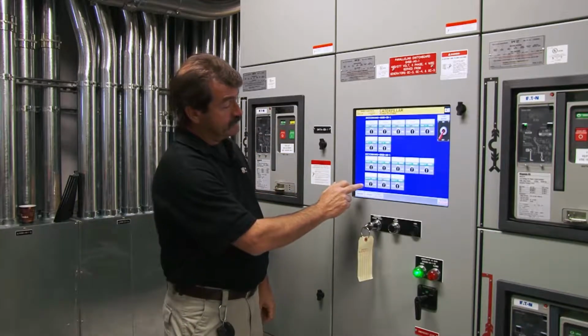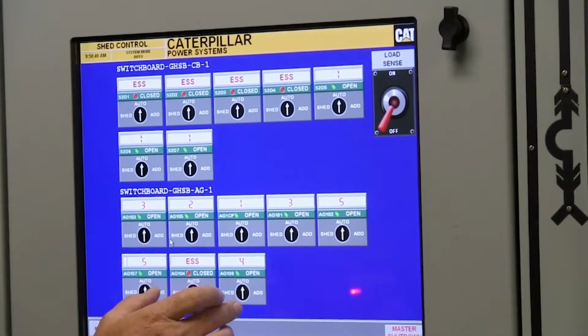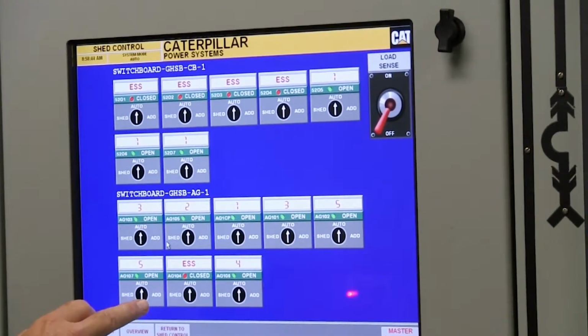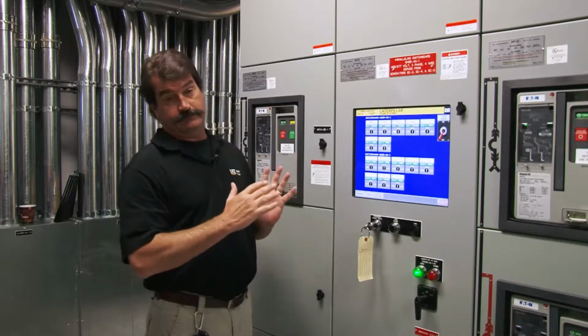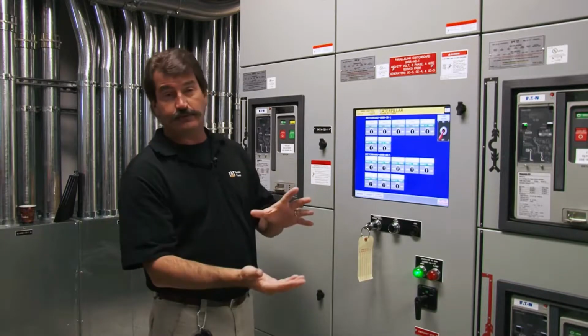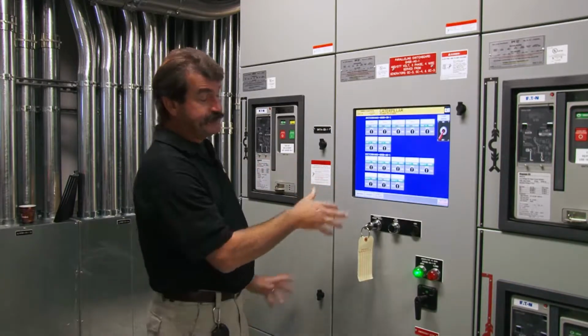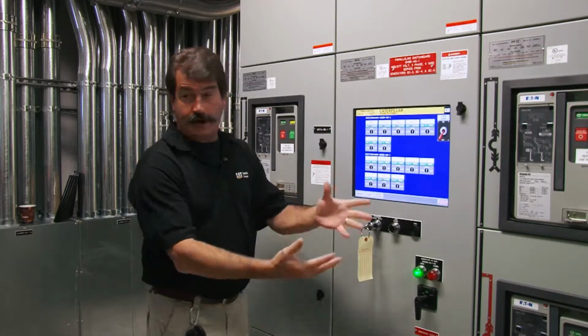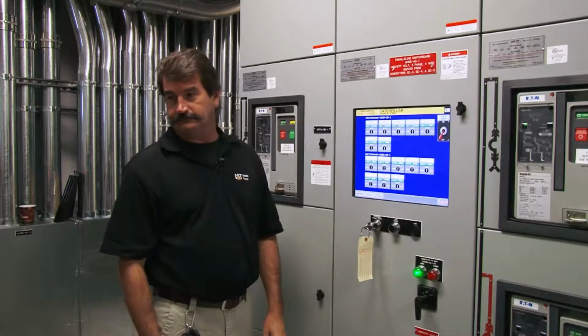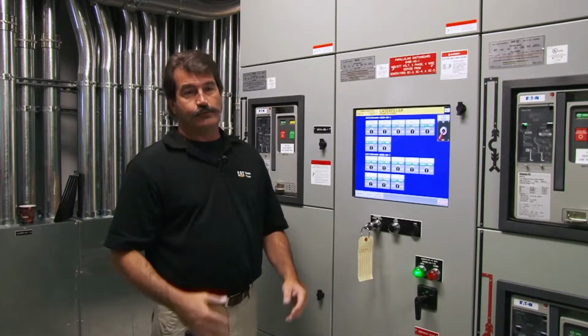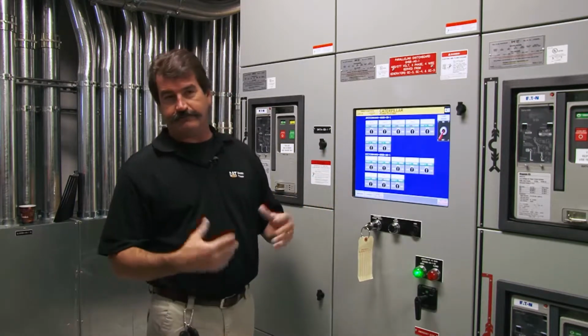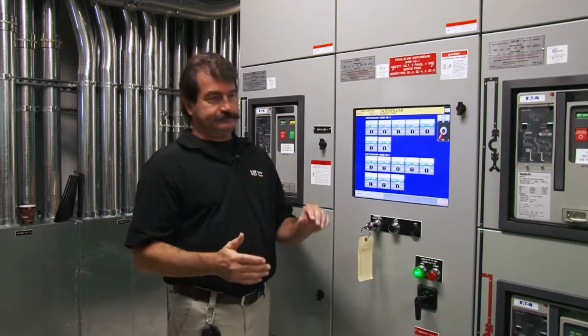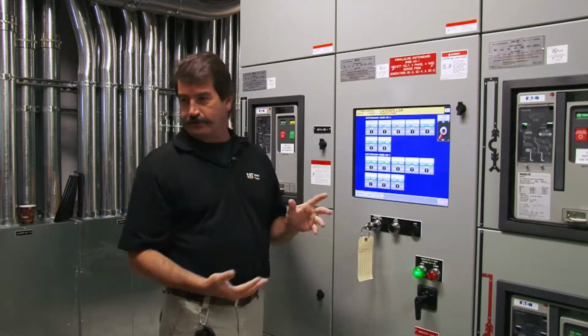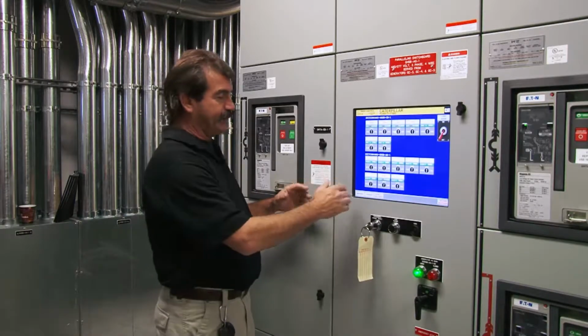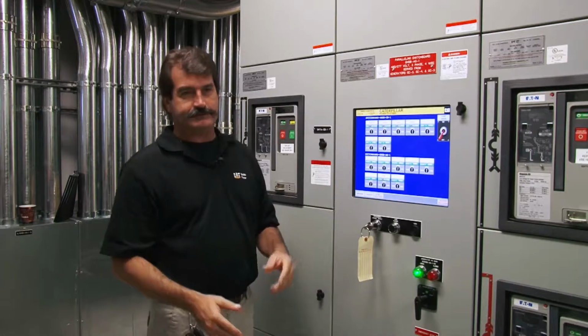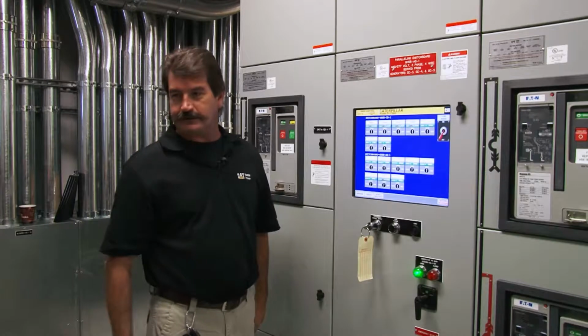You can also go to this switch that's pointed straight up into auto. You can take it to add or to shed, and it will either manually or remotely close or open that breaker. If you keep it there, we will not try to do anything else to that breaker after that. If you put number 5 in shed, we will not try to close that breaker even though it's set. We usually do that if you need better control of something, like if you're doing maintenance work and want that breaker always in shed so it doesn't try to close in.